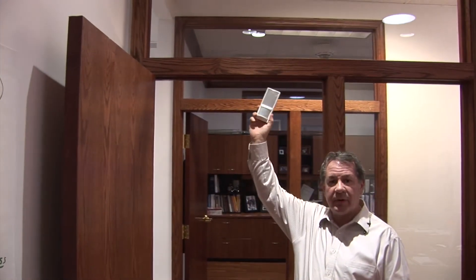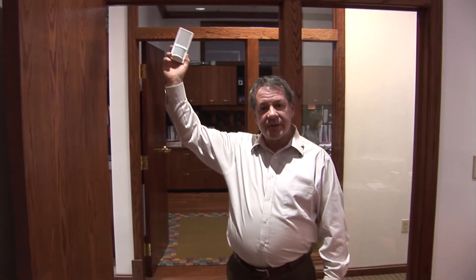Occupancy sensors are one of the most difficult sensors to install in a building because you don't know where you'll get problems with motion that isn't relevant to someone being in the room. These rooms have glass panels next to them — if we mounted the sensor in the wrong direction, we might be turning lights on and off every time someone walks past. If we had made that mistake with a wired sensor, it would be an expensive repair to fix. With wireless, we can test the product by moving it to different spots around the office and deciding where we want to put it. It wirelessly communicates to the Can2Go controller above the ceiling with no wires required.